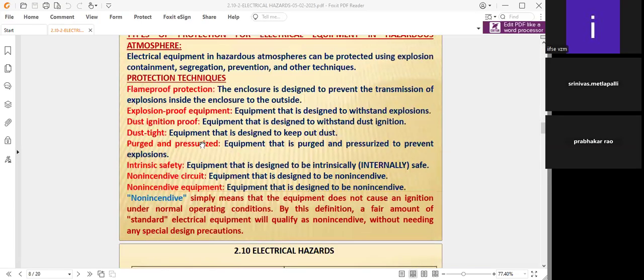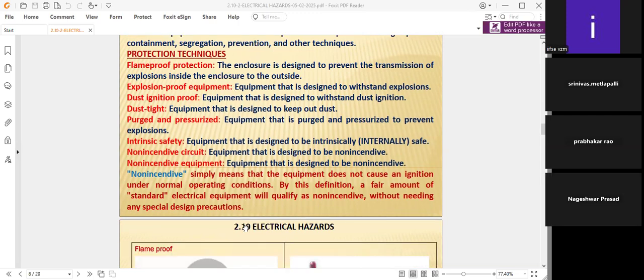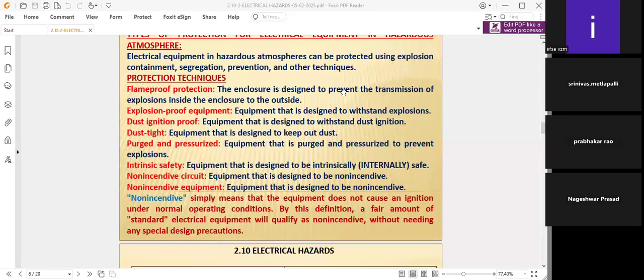So we have to take care of the hazardous areas and electrical equipment. These are the protection types: flame-proof, explosion-proof equipment, dust ignition-proof, dust-tight, purged and pressurized, intrinsic safety, and non-incendive circuits, which are also very important. We will discuss them in the coming slides. The enclosure is designed to prevent the transmission of an explosion from inside the enclosure to the outside. That means flame protection will be provided in the circuit itself or in the equipment itself.